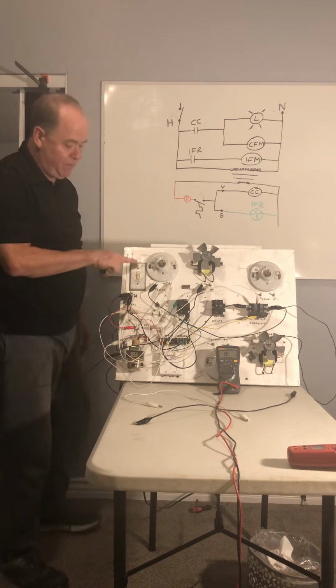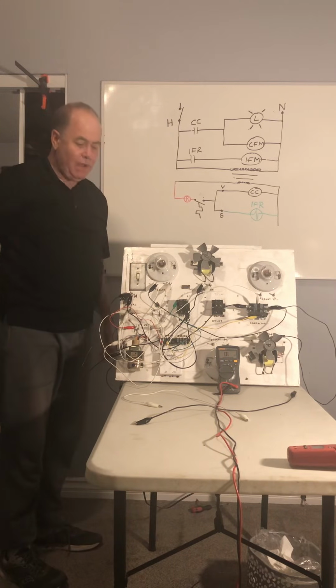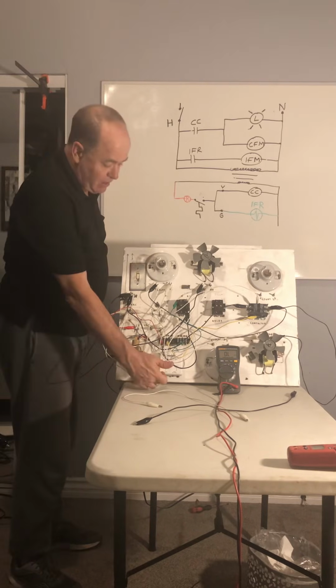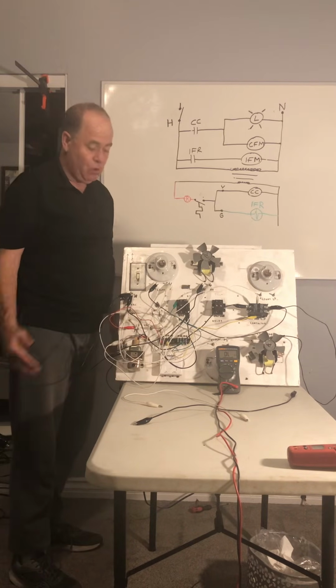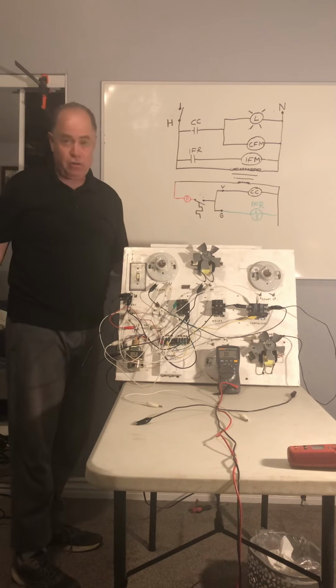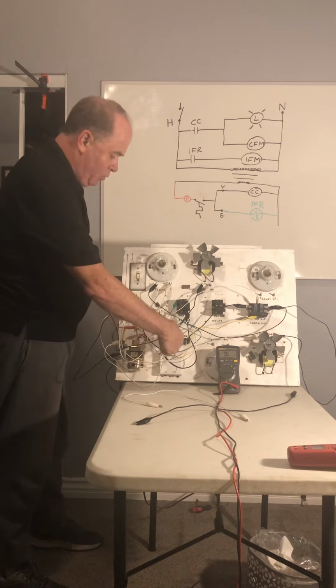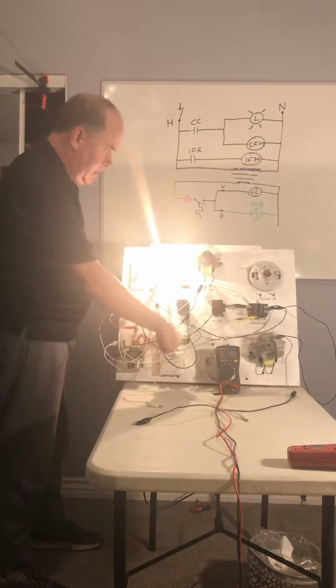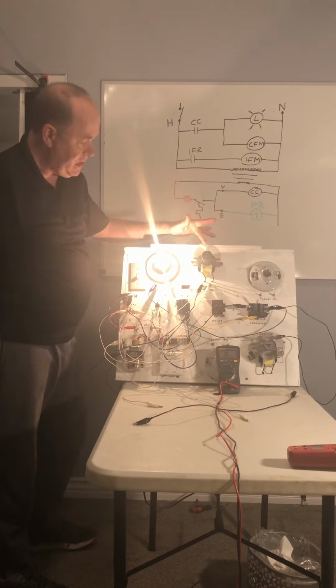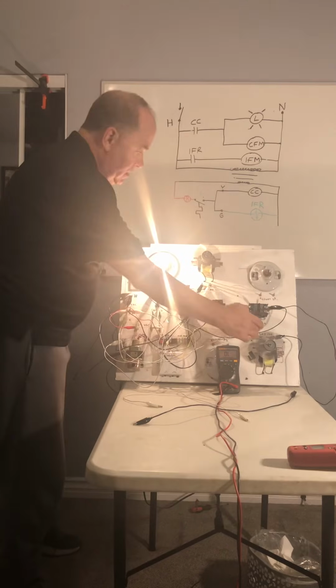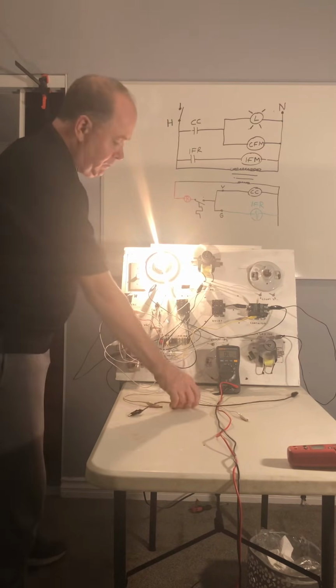So I've plugged it in, I've turned the power on, I've already made sure that we have the thermostat set on the subbase to cool and auto. And let's say I want it cooler in here, then I would lower the set point on the thermostat, and lo and behold, the compressor comes on, the evaporator fan comes on, and the condenser fan motor comes on. And then we can take a couple of readings with our meter.